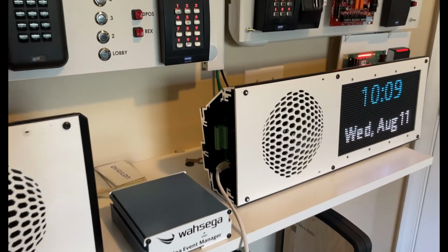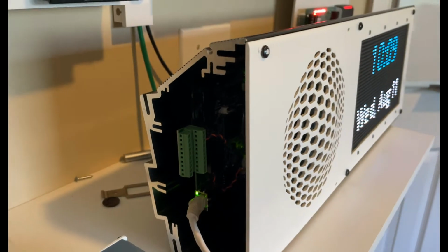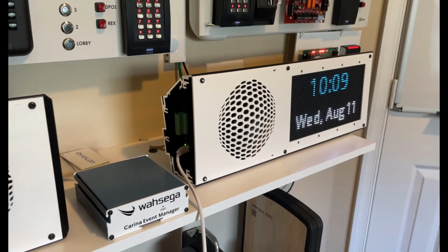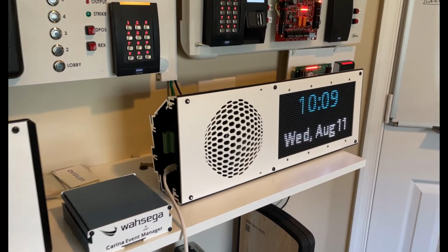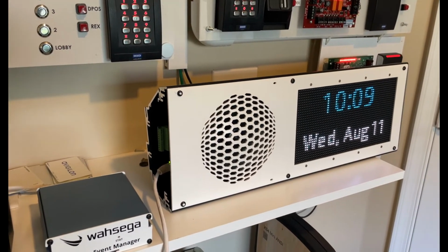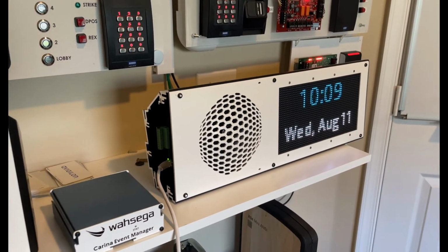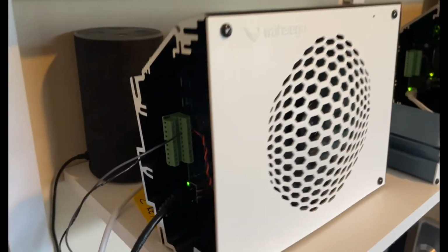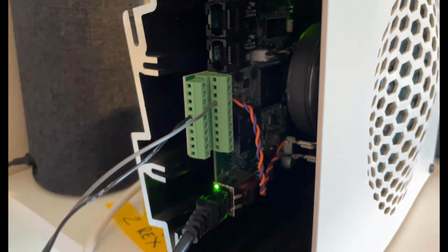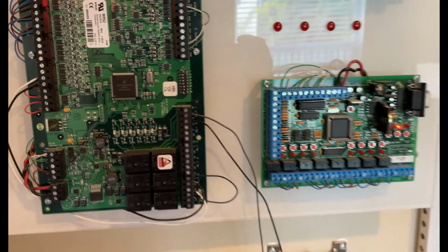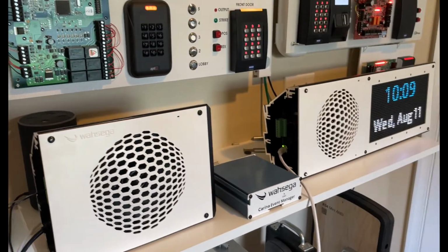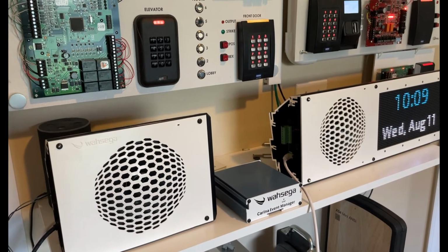A couple of things in here. I removed the panels on the side so you can see the network connection right there, and that green Phoenix connector there is the input points. So you can wire from an output on a Mercury board into one of those speakers and trigger an event or a notification based on that. Each one of those speakers has that. That one right there, I have it connected. So here is one of their inputs connected to an output on a Mercury board. Let's go ahead and take a look at the software and see how that's done.